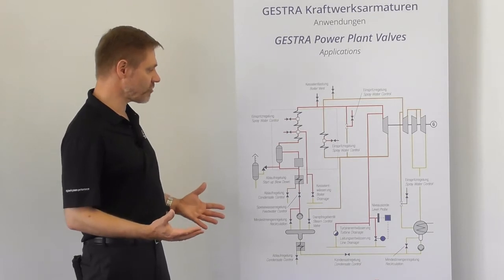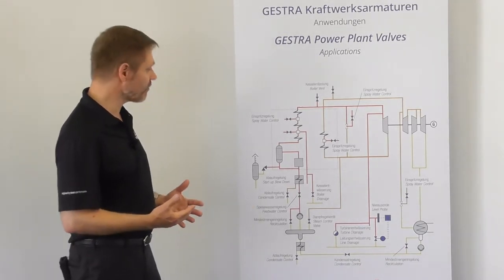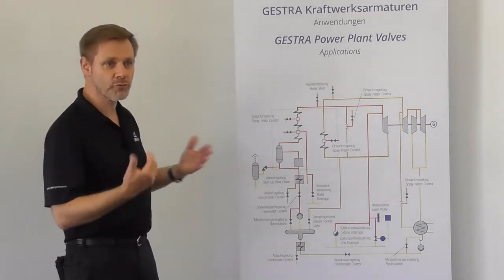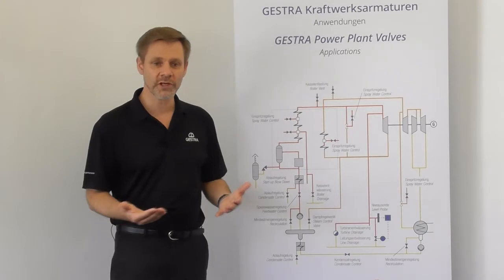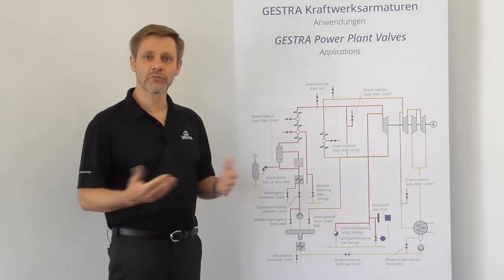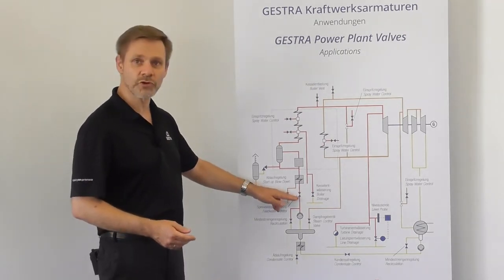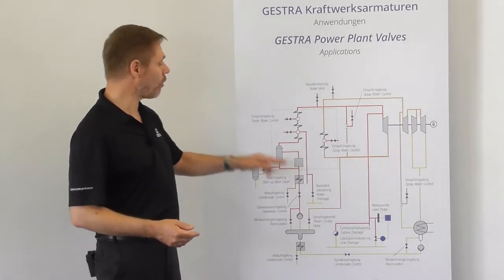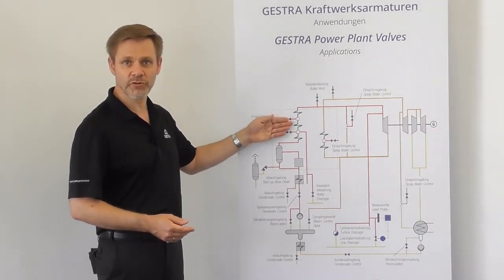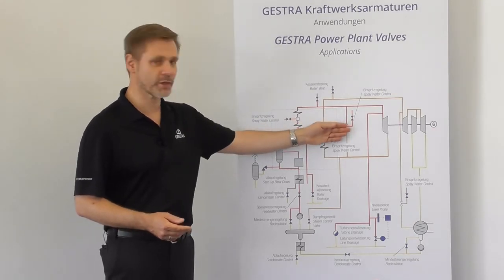Typical applications for our severe service control valves are the blue colored items here. These are valves for steam, water, and flashing water service. Examples for water applications are the feed water control valve or the spray water control valves at the steam coolers between the super heaters or reheaters or at the bypass stations.